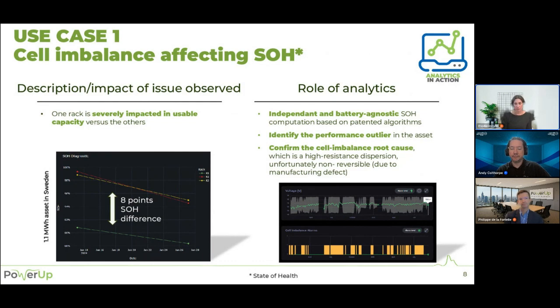All of these examples will highlight how the PowerUp solution really captures anomalies that the BMS couldn't detect or couldn't solve. Let's start with the first one, a typical site in Sweden, an installation of 1.1 megawatt hours, where we'll see that cell imbalance really affects the available capacity of a battery rack.